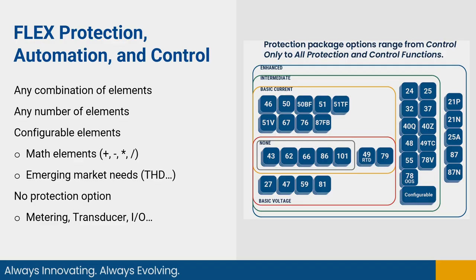If you move up to the intermediate package, that includes the basic voltage elements along with the basic current elements. And then if you go to the enhanced package, it enables all the protection available in that particular BE1-FLEX. With this capability, the BE1-FLEX can be upgraded in the field simply and easily via the protection packages with an encrypted firmware file. So you do not have to send the relay back to do upgrades. It can be done in the field.